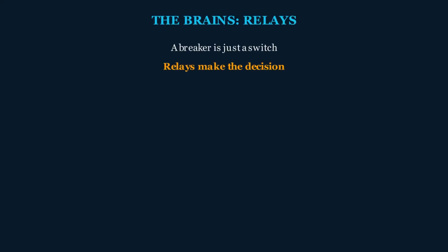A circuit breaker is just a switch. How does it know to open in a few thousandths of a second, in the middle of the night, with nobody standing there? It doesn't. The breaker decides nothing. The decisions are made by protective relays, and they're the part of the substation you can't really see, because they live in that small building at the edge of the yard, the control house.